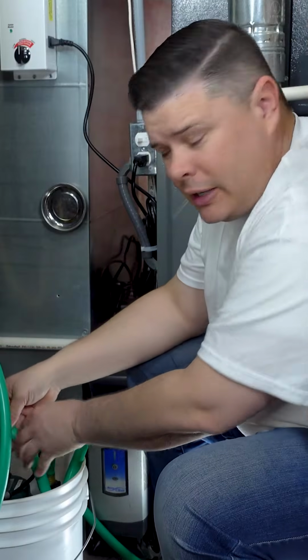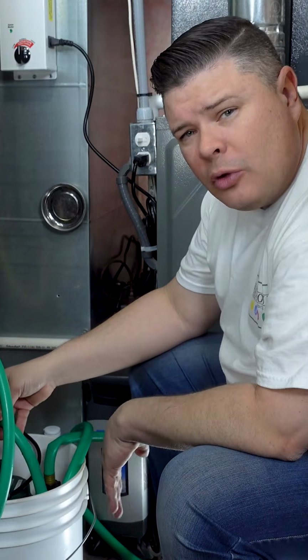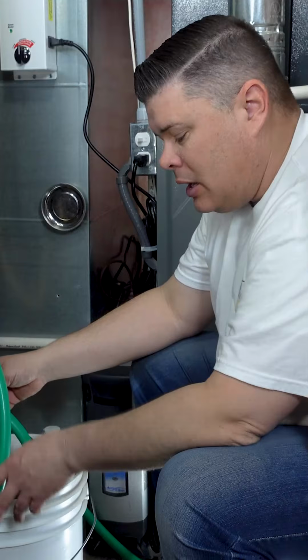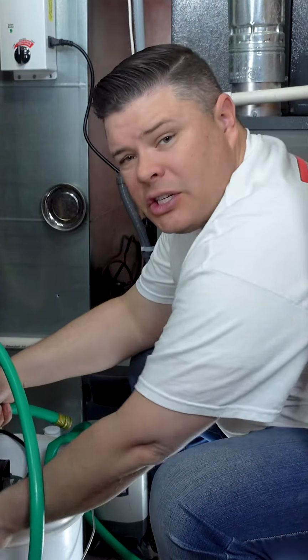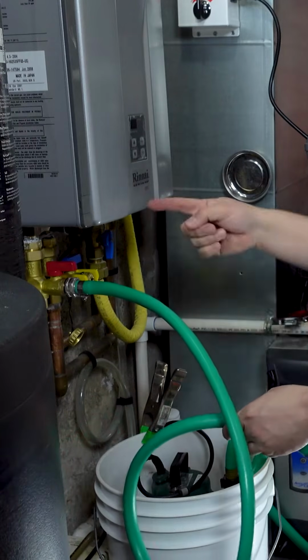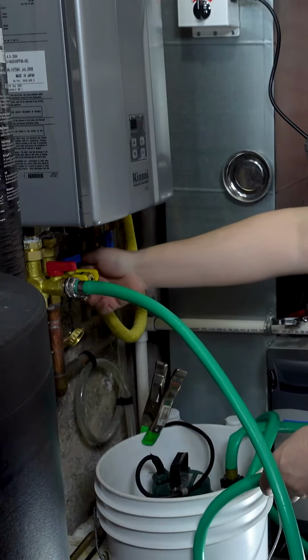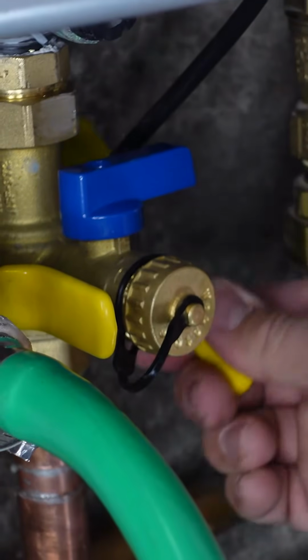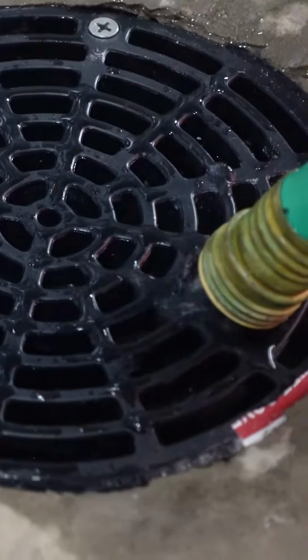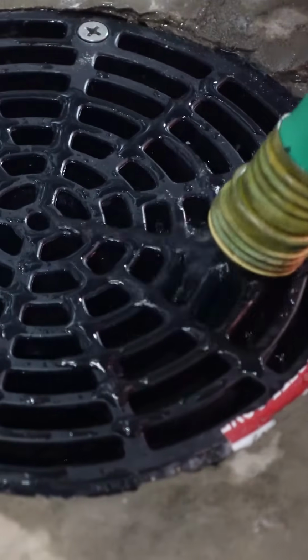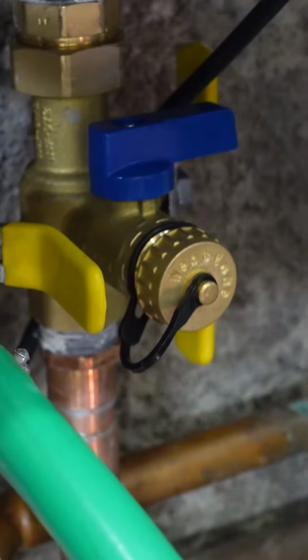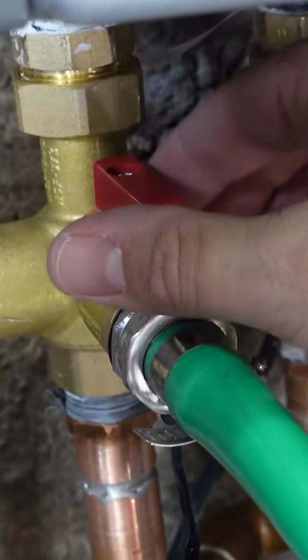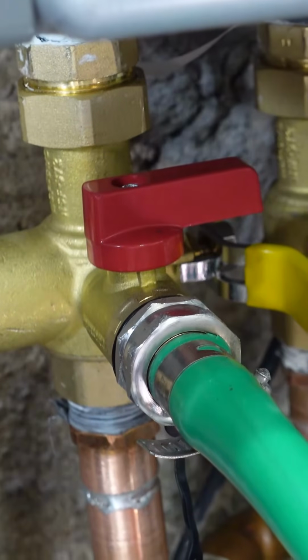I have a floor drain in this room, so I'm going to run to the floor drain, but if you don't, you can run to a bucket because we're going to flush it with the fresh water coming into the tankless by opening this valve. Once you're done with that, close the supply valve and then make sure all of the valves are closed and disconnect the hose.